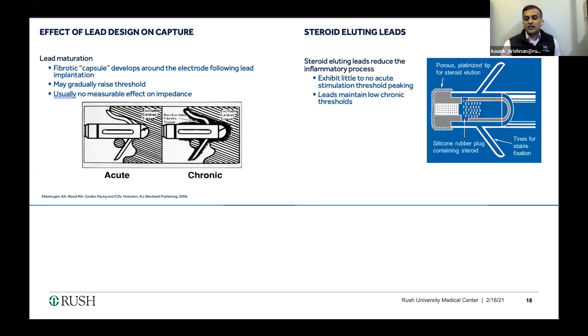Steroid, as I mentioned, is one way to decrease the ability of that interface to prevent capture. Most leads that are now on the market have a little bit of steroid at the end that prevents the acute stimulation threshold from going up too high. You don't want the lead to be pacing when you place it in someone who's dependent, and then 24 hours later, when they're in their room, they lose capture because the threshold went up to a very high amount, and then you have inadequate output to stimulate the myocardium, and then they may go asystolic or have a very slow escape and have syncope.